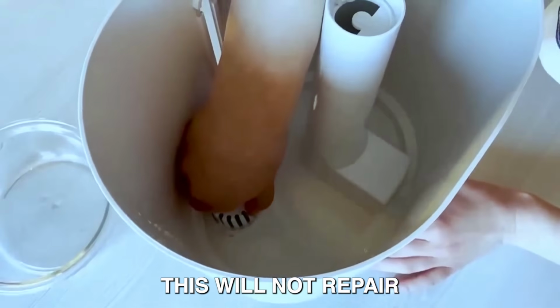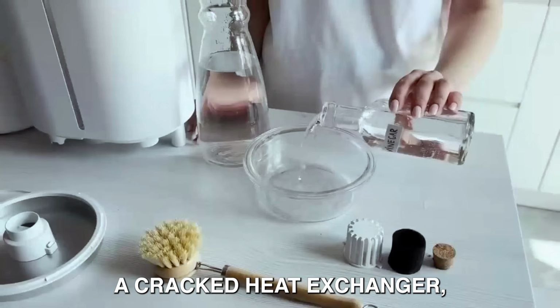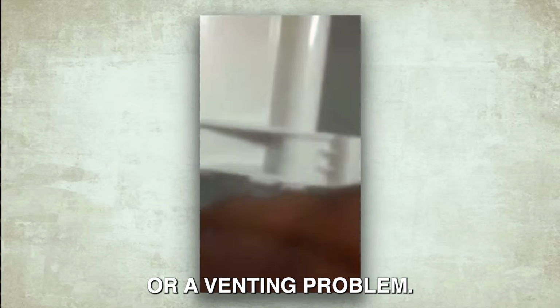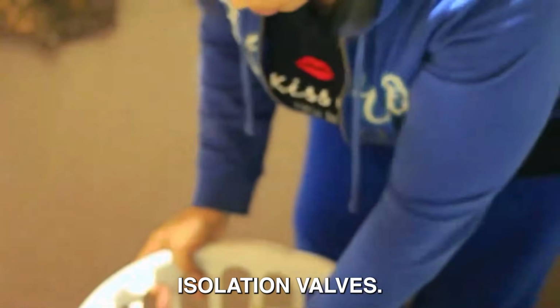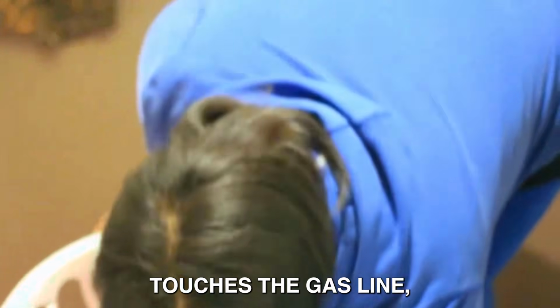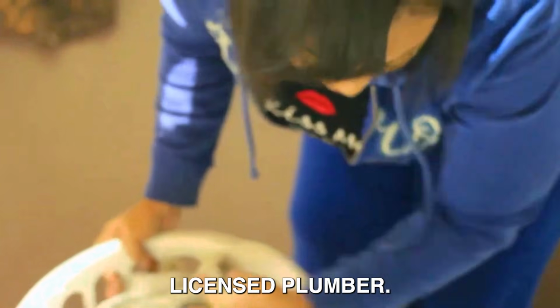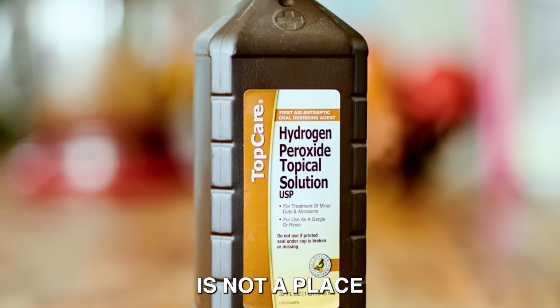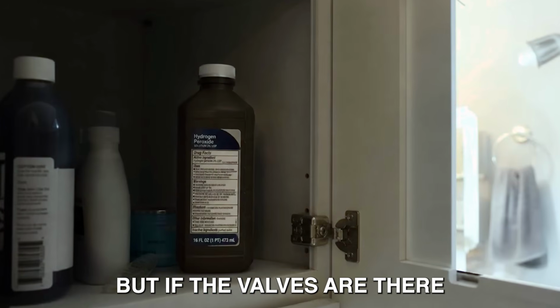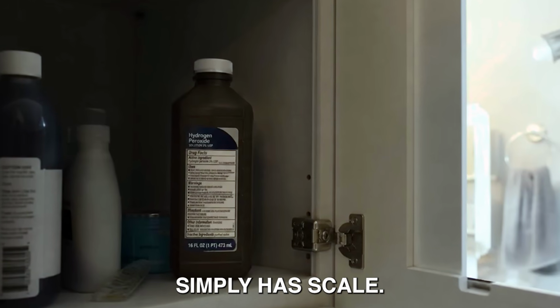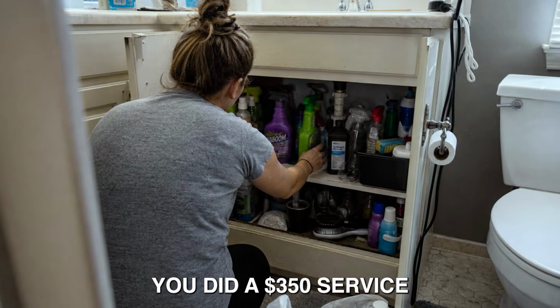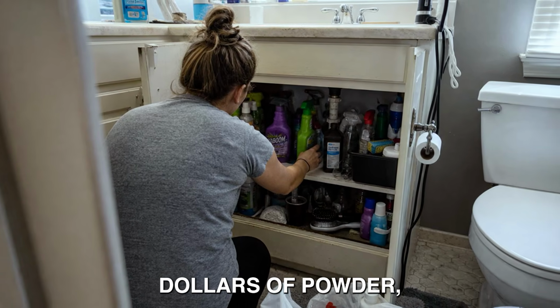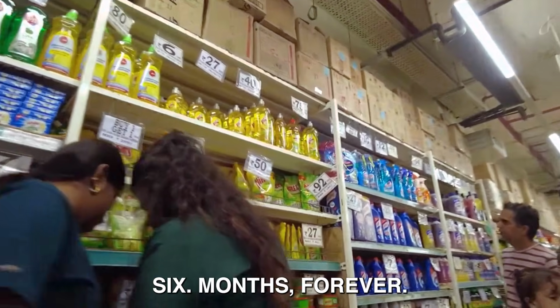Now the honesty. This will not repair a cracked heat exchanger, a failed igniter, a bad flow sensor, or a venting problem. If your unit has no isolation valves, or if the work touches the gas line, you must call a licensed plumber, because gas is not a place to save money. But if the valves are there, and the unit simply has scale, you did a $350 service for about $8 of powder, and you can do it every 6 months forever.